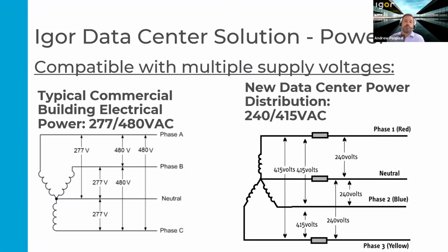So some newer power center or newer data center power designs incorporate a 415 volt, 240 volt AC solution, which is much more friendly and compatible with your typical IT equipment range, which typically runs from 100 to 240 volts. So it matches perfectly from a PoE aspect as well. The higher the input voltage to those PoE switches, the more efficient the power pass through, the power transfer through those switches. So, from our standpoint, any new data center that's incorporating the newer power distribution design is getting to be as efficient as possible. So with that, I will turn it back over to Kim and Matt.